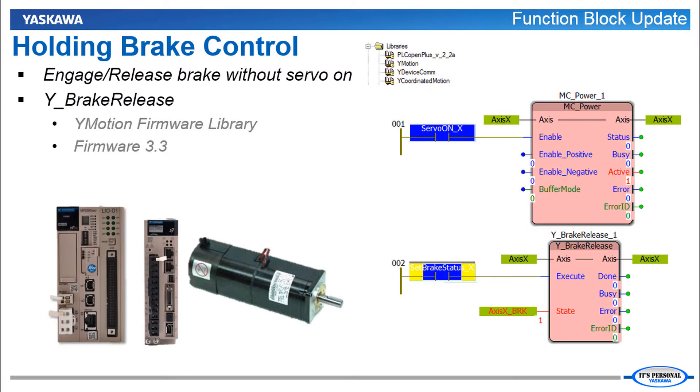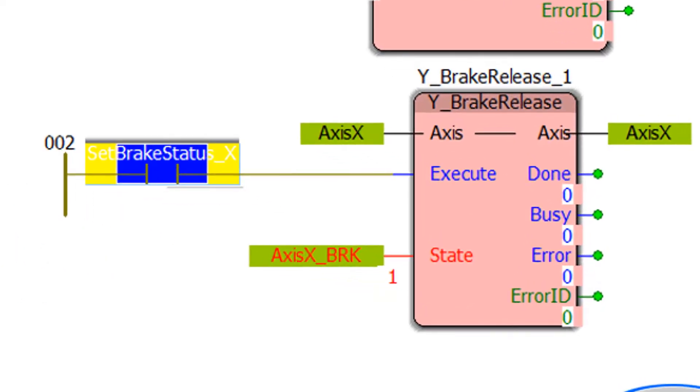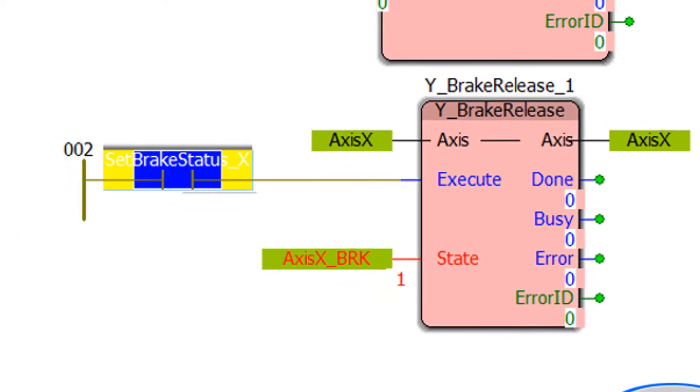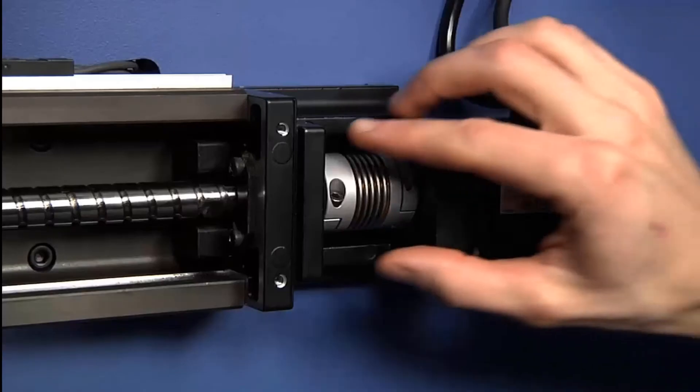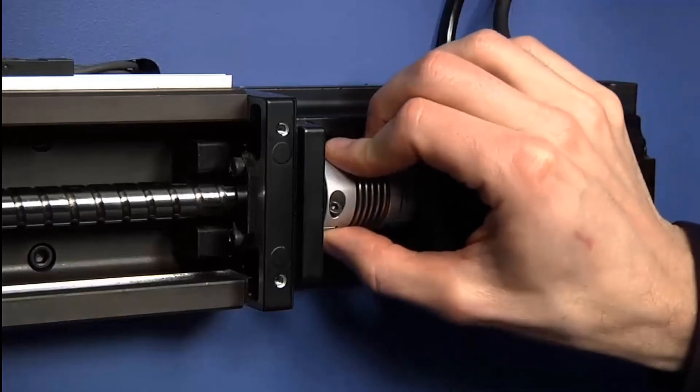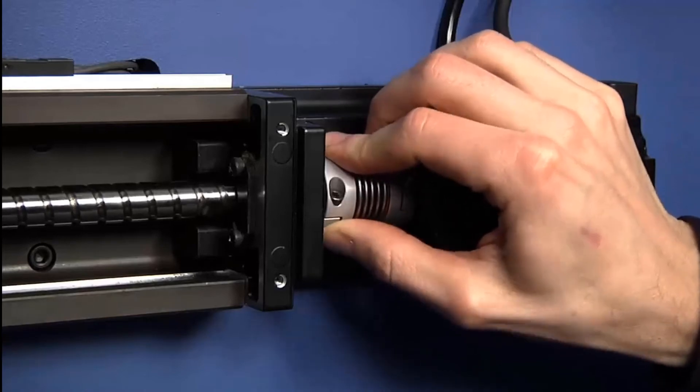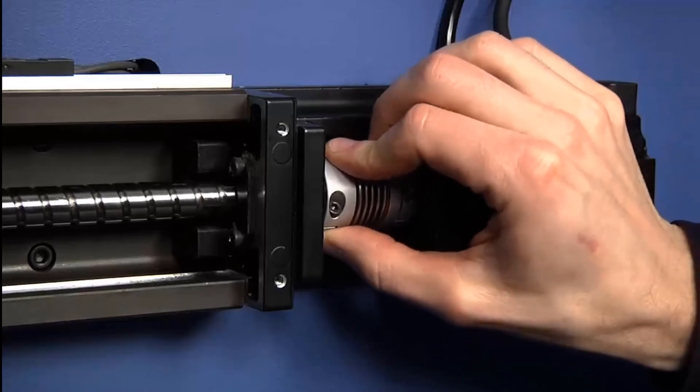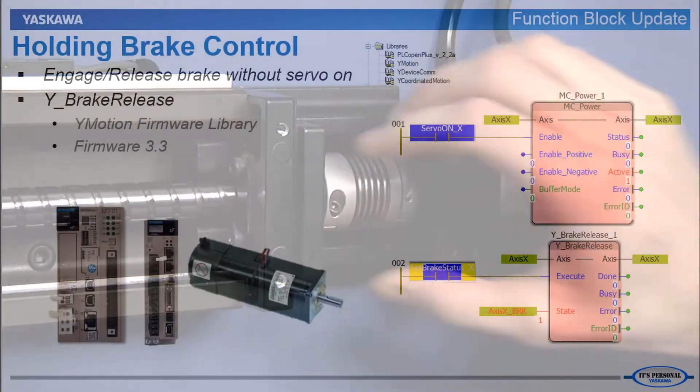Control of the holding brake is improved. The programmer can set conditions to release the built-in holding brake of a servo motor using the function block Y Brake Release. This way the axis can be moved externally with the servo off. For example during mechanical setup or calibration or troubleshooting.